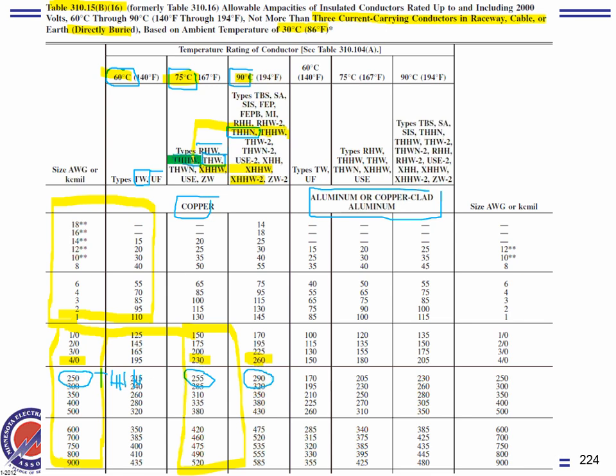Here's another one, number 6. Number 6, have no idea what the lugs are. The installation is THHN. So it's rated for 90, right? So when I size equipment under normal operating condition, how much can I size this equipment for? 55 amps. Now here's a trick. 55 amps for normal operating. How about if I want to derate? Which amp should I use for derating? 75.